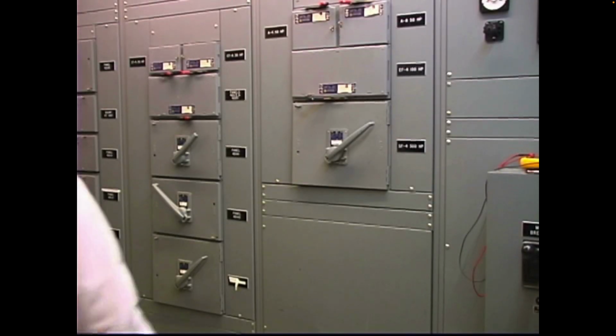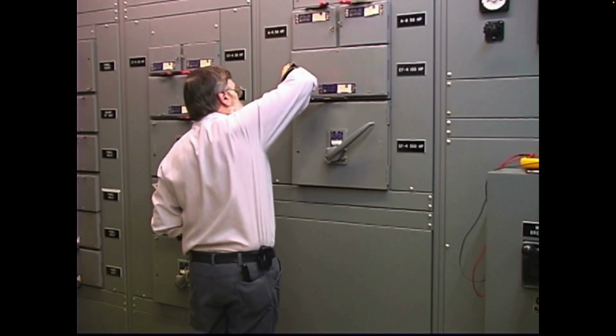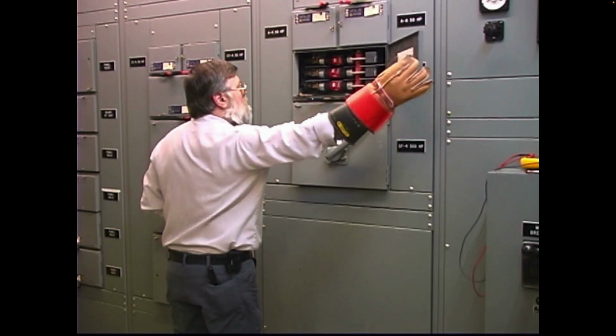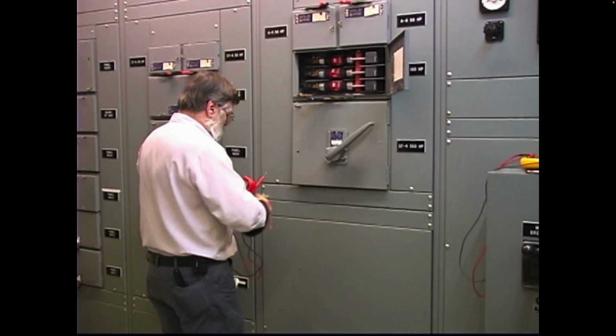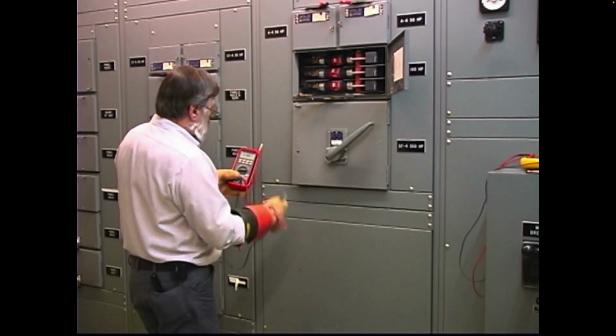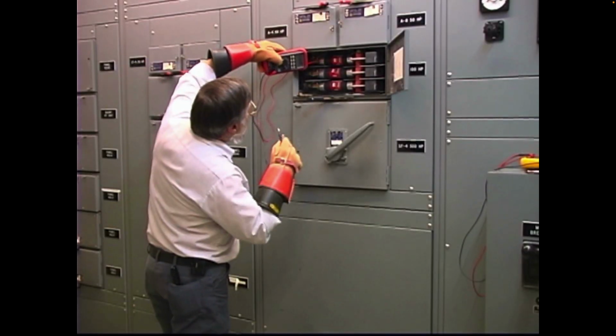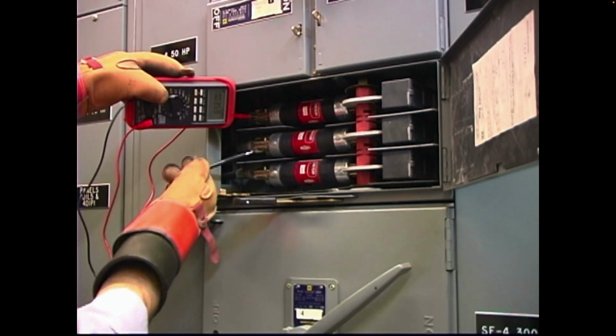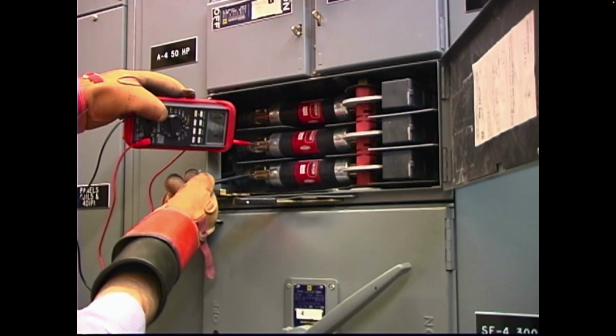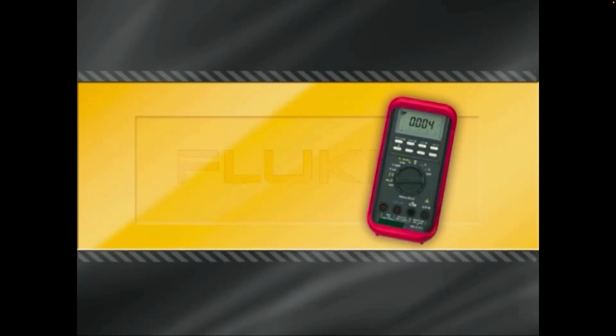Let's take a closer look at why transients are so dangerous. In this example, a service technician is making a phase-to-phase voltage measurement on a 480-volt motor supply circuit. This is a CAT 3 environment. A major voltage transient caused by load switching or a nearby lightning strike was large enough to cause an arc to strike inside the meter.